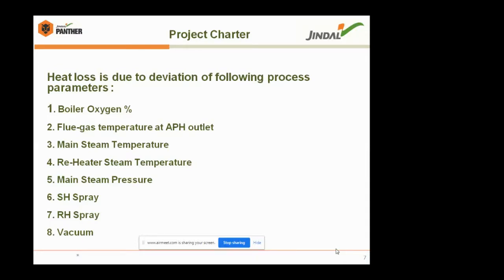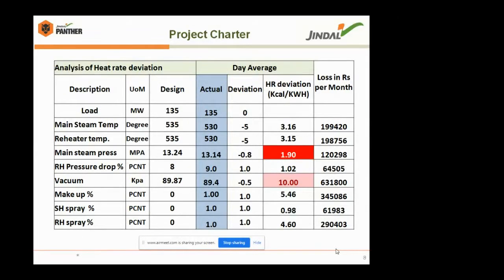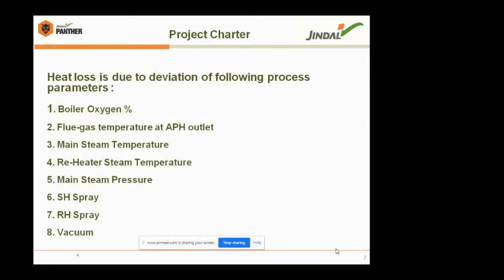As I have said earlier, our load is very variable, meaning in a day we are varying the load around 50 times within the range of 0 to 180 megawatt. Because of that, we are facing a lot of problems maintaining these parameters at the design value. If the actual parameter deviates from the design value, it will result in loss of heat in the form of flue gas.